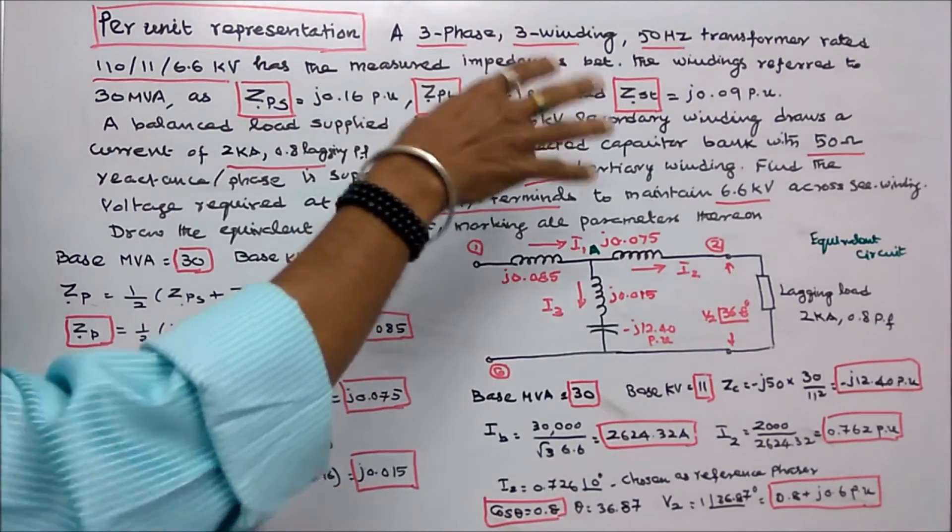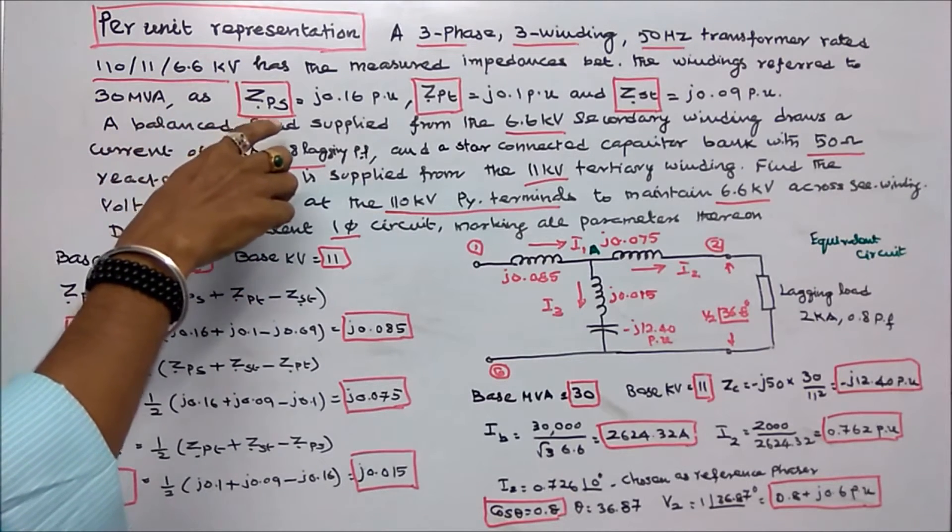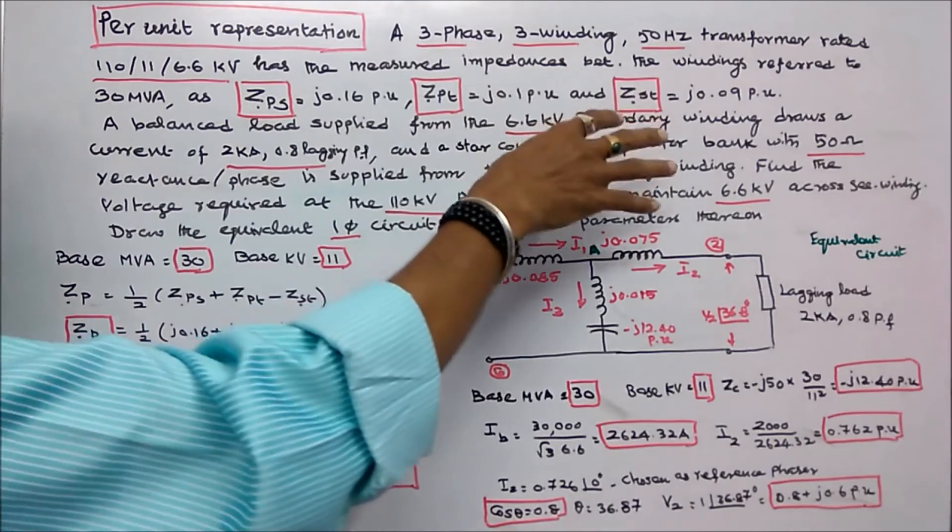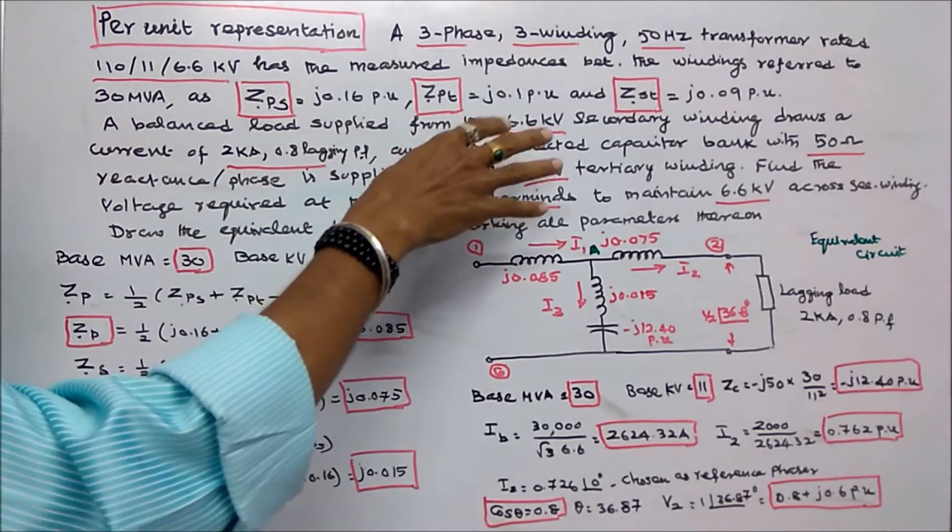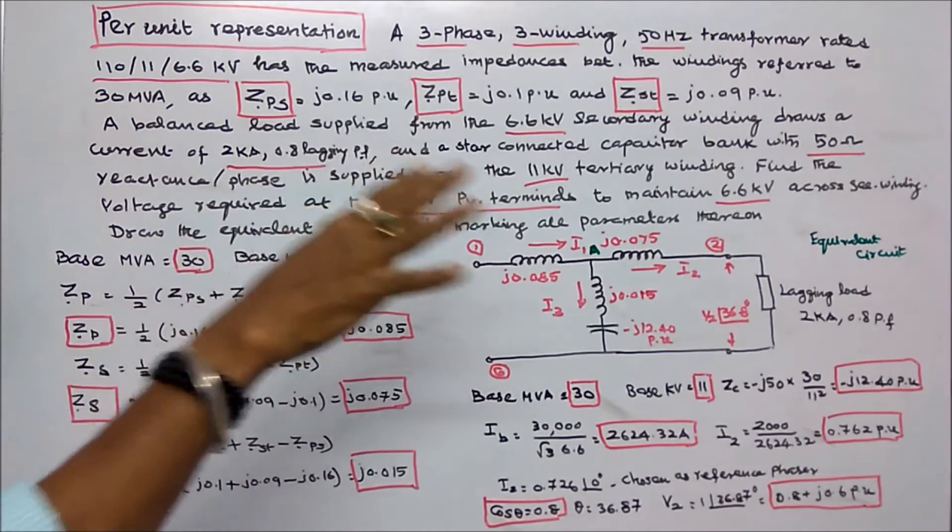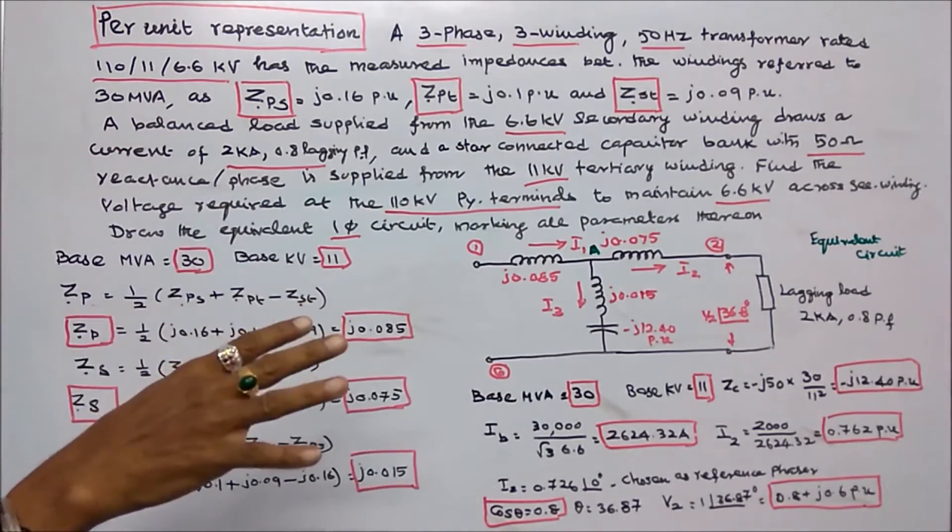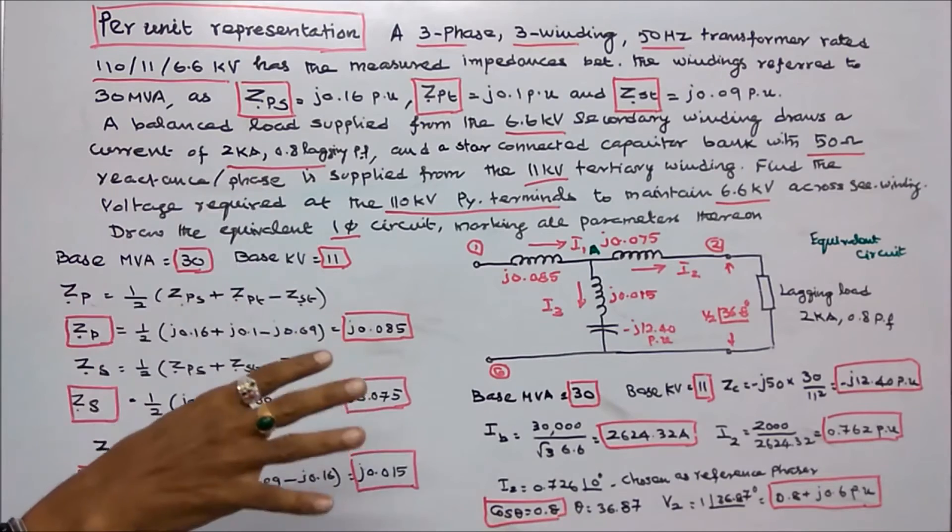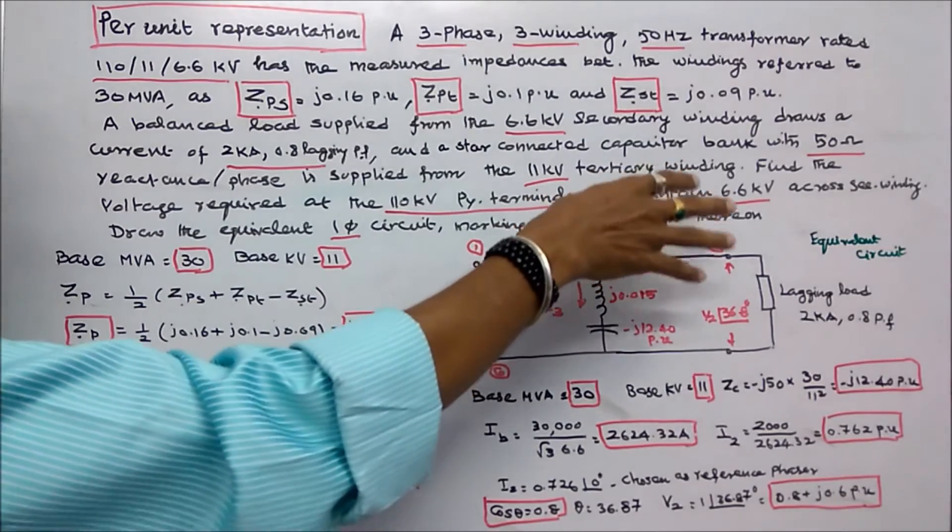The measured impedances between the windings referred to 30 MVA as Z per unit PS is equal to J.16, Z per unit PT is equal to J.1, Z per unit ST is equal to J.09. A balanced load supplied from the 6.6 KV secondary winding draws a current of 2 kA 0.8 power factor lagging. A star connected capacitor bank with a 50 Ohm reactance per phase is supplied from the 11 KV tertiary winding. Find the voltage required at the 110 KV primary terminals to maintain 6.6 KV across secondary winding.